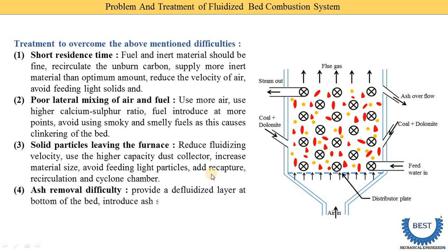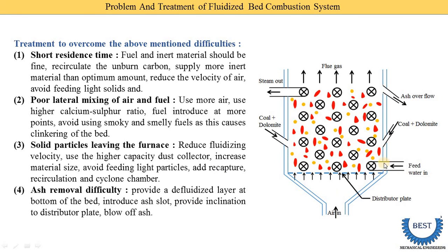The fourth problem is ash removal difficulty. To avoid this, we have several options: first, provide a defluidized layer at the bottom of the bed on the distributor plates, followed by the fluidized bed layer. Second, introduce ash slots on the bottom parts of the vessel. Third, provide inclination to the distributor plate — instead of a horizontal plate, use an inclined plate so ash removal is easier. Fourth, use a blow of ash — use a fan to remove ash from the distributor plates.